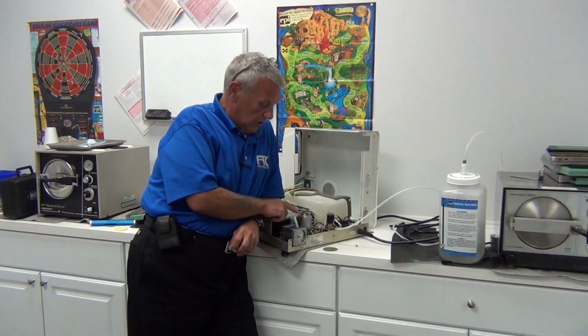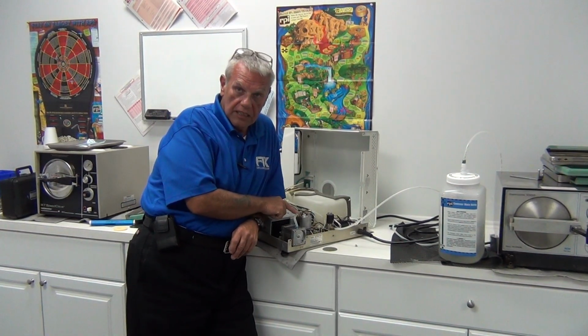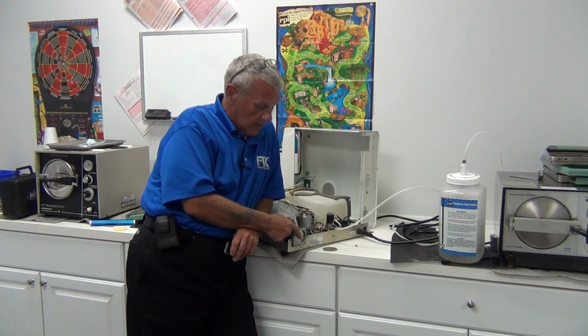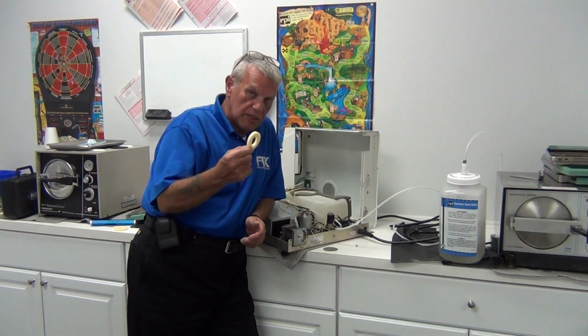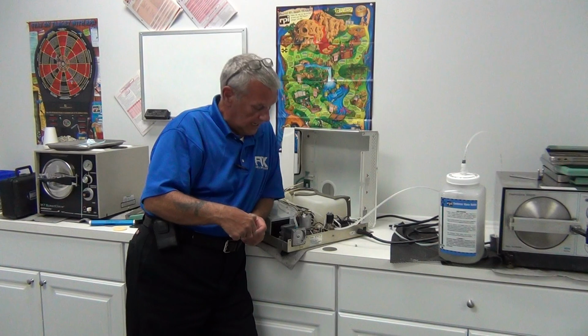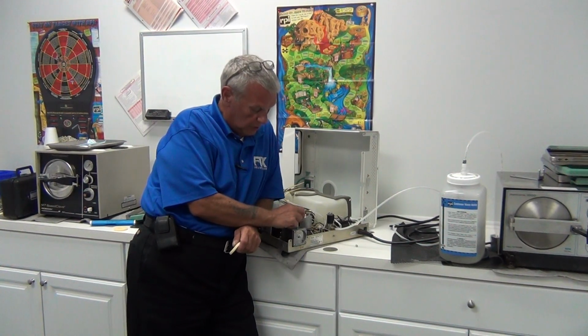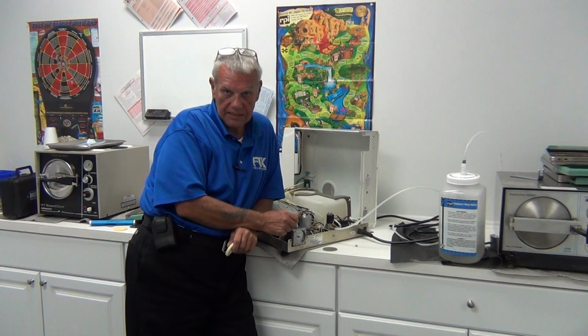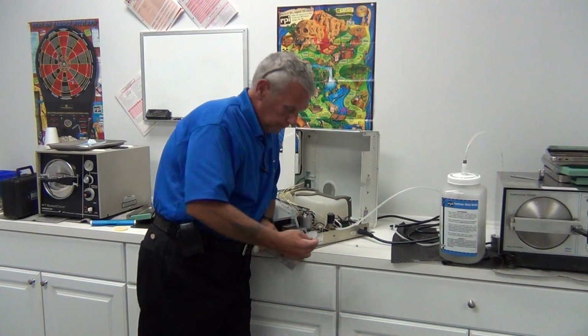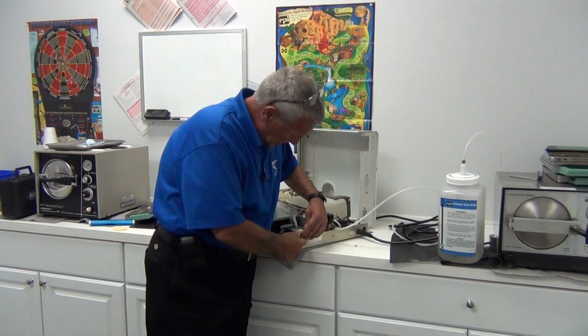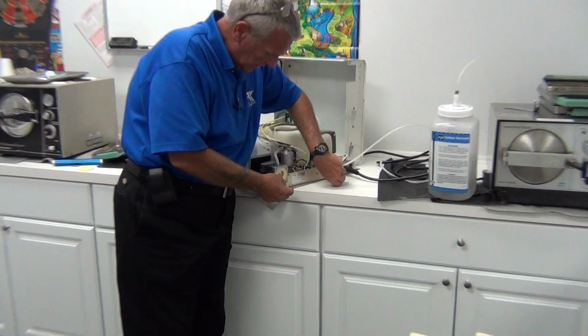So once every 2 years you replace the check valve. Every 3 months you replace the filter. And you also check the check valve tubing, as we stated earlier, for condensate. To replace the filter is very easy. Replace it the same way that it came out.